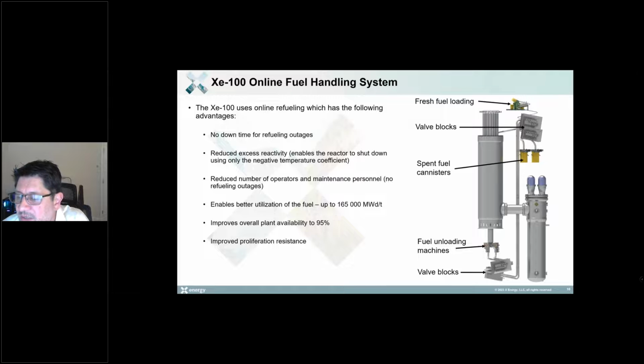If it's not spent, it gets recirculated back to the marshalling block and inserted back into the reactor. On average, a pebble passes through about 6 times, and that's what helps us get a very high burn-up and improves our overall plant availability to around 95%. Once fuel enters the fresh fuel loading station, no human interaction is ever required.